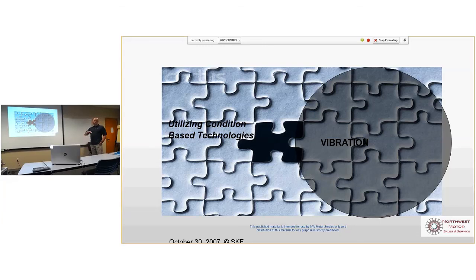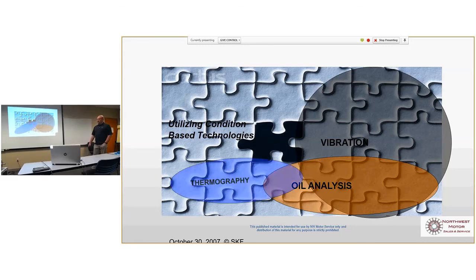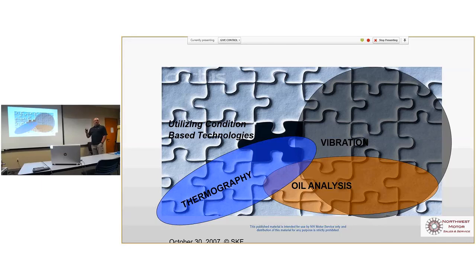Based on whatever you enter in there, based off those exact bearing sizes, we can tell you if the bearings are failing or not. So that's really good. And you can see things like misalignment, mechanical looseness, soft foot, all that kind of stuff. So vibration is pretty strong, and I definitely recommend it. Oil analysis is mainly for bigger motors that have oil bearings. Thermal, you can see if the motor's running too hot, of course, with the bearings, and it's really strong inside the electrical panels, finding loose connections. And then electrical testing is what we're going to talk about.